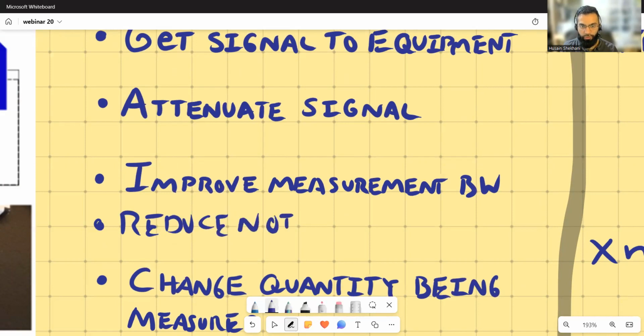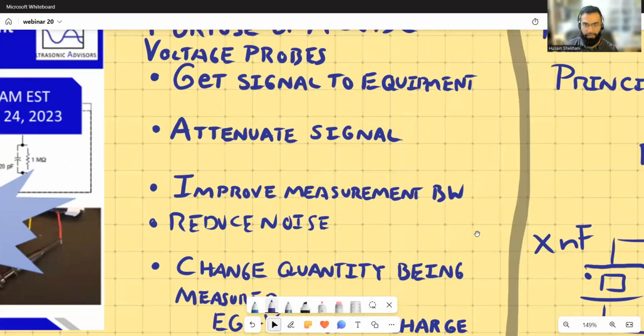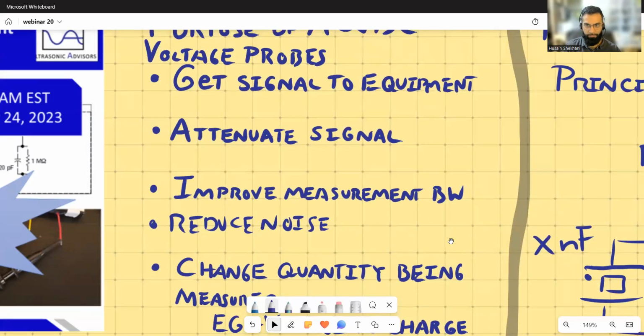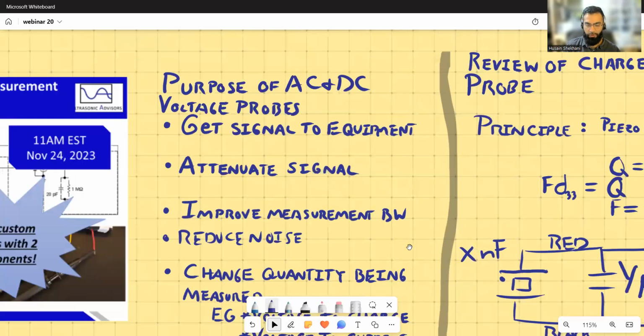Traditional oscilloscope probes are carefully designed. The design has probably been iterated over and over again, so it's nothing new to many people. But there's a lot of shielding. There's resistive wire used. It's not just two components in series or in parallel, and that's all it is. There's a bit more going on to make that whole construction, which becomes challenging to replicate. But rather than doing that, why not make your own probes, which are simpler and don't require compensation? I think you'll be pretty confident using them for specific applications, especially lower frequency, lower than 300 kilohertz.